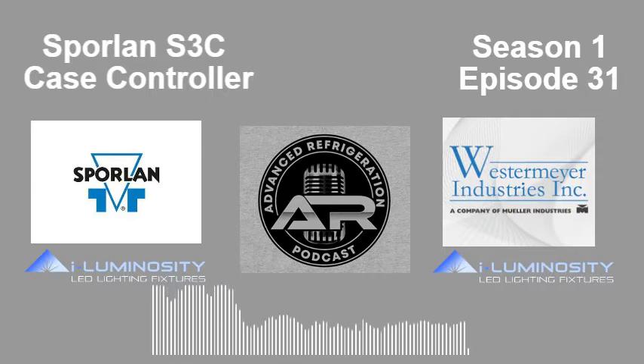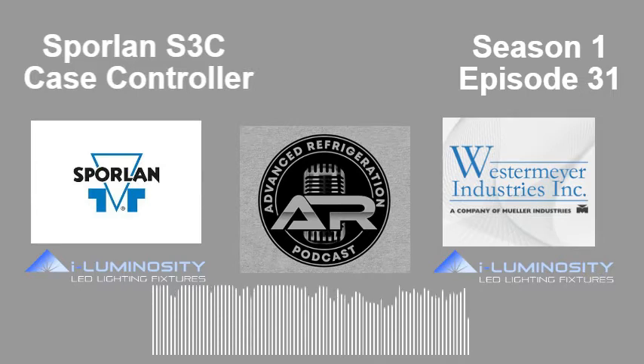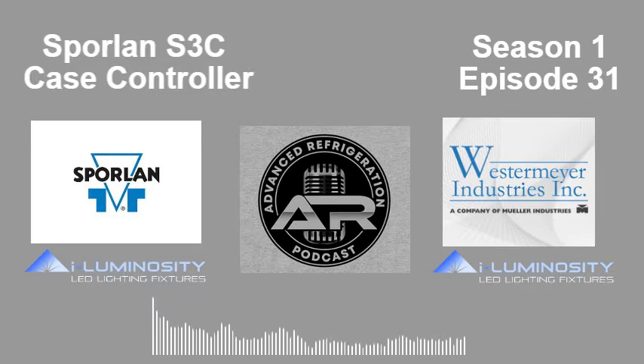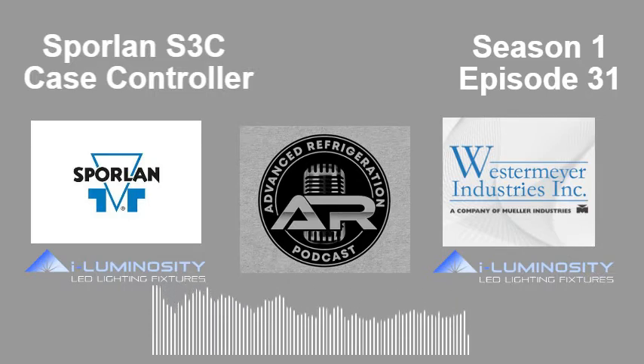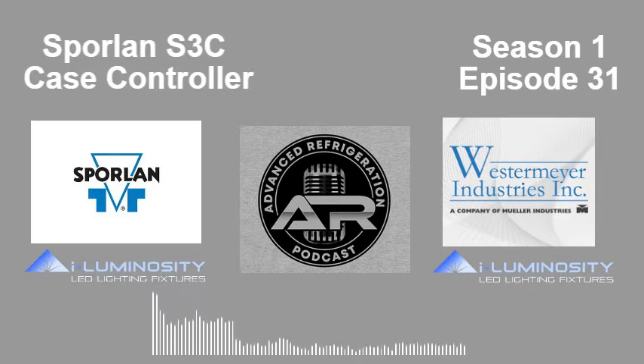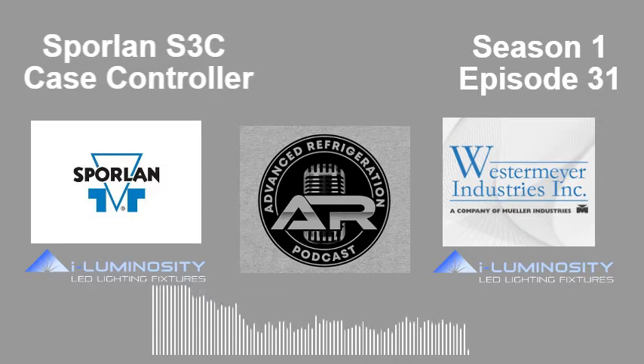We've got a relay to handle fans, to control fans in the case, lights, defrost heaters, anti-sweat heaters, even a straightforward electrically actuated, electronically controlled EEV, if you will, for superheat regulation and door status. And then we've got temperature and pressure, occupancy and humidity, should you decide to use those functions. A lot of times they don't use everything that we offer.